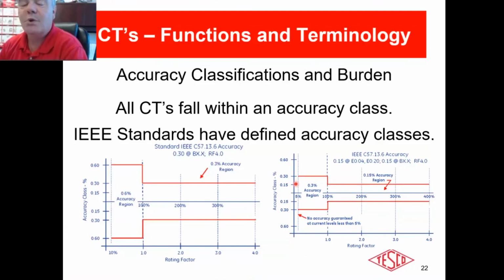Why is 1% important? Well, shoot, even at a 400 to 5, the 5% was still 20 amps. Plenty of facilities will be drawing less than 20 amps off shift, okay? It's probably right at the limit, but if you go down to 1%, now you're talking about going down to 4 amps. There's almost no possibility that facility is ever going to get down to 4 amps. So basically, by using the newest extended range instrument rated transformers, you effectively can guarantee that you will be correctly and accurately metering them all the way down to virtually zero, 4 amps, 8 amps, 2 amps, depending on the size of the transformers. And your accuracy will maintain throughout the range, all the way up to the limit of the thermal rating factor. Now, some of those don't have a thermal rating factor as high as 4.0.